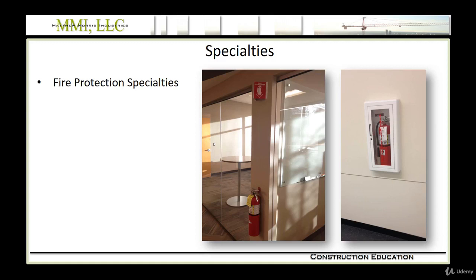Okay, the type of fire extinguisher that's used is required by code, depending on the fire hazard. So the designation in the United States would be Class A for ordinary combustibles, Class B for flammable liquids or gases, Class C, electrical equipment, Class D, combustible metal fuel sources, or Class K, a cooking fire. Other locations, such as the UK, are similar but not exactly the same.